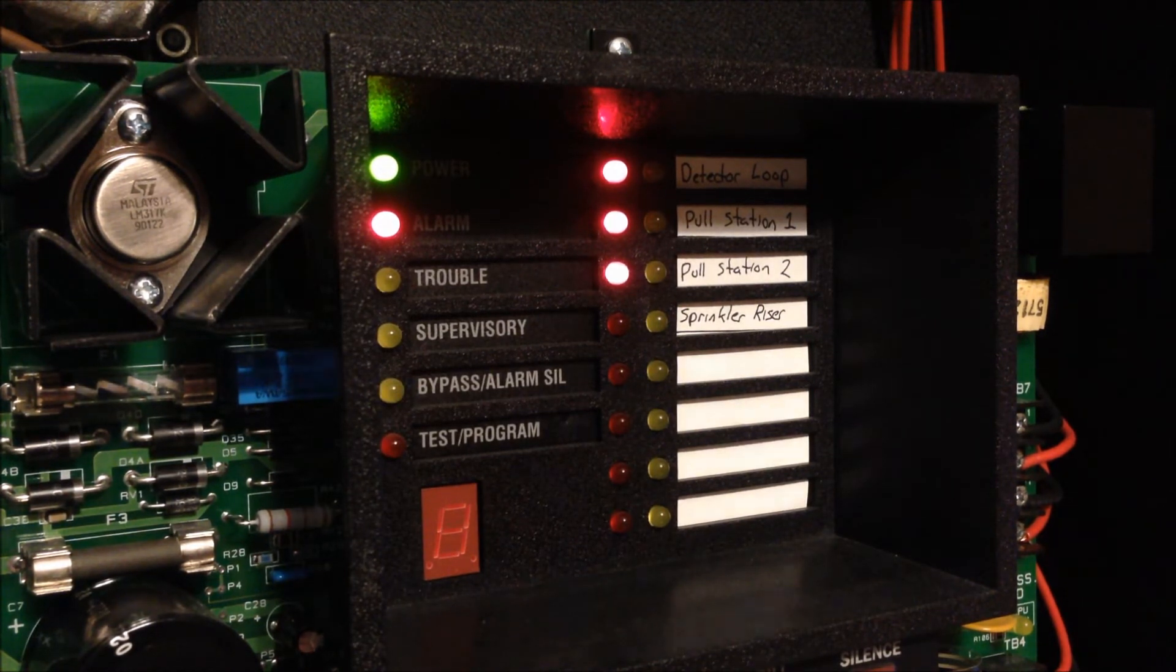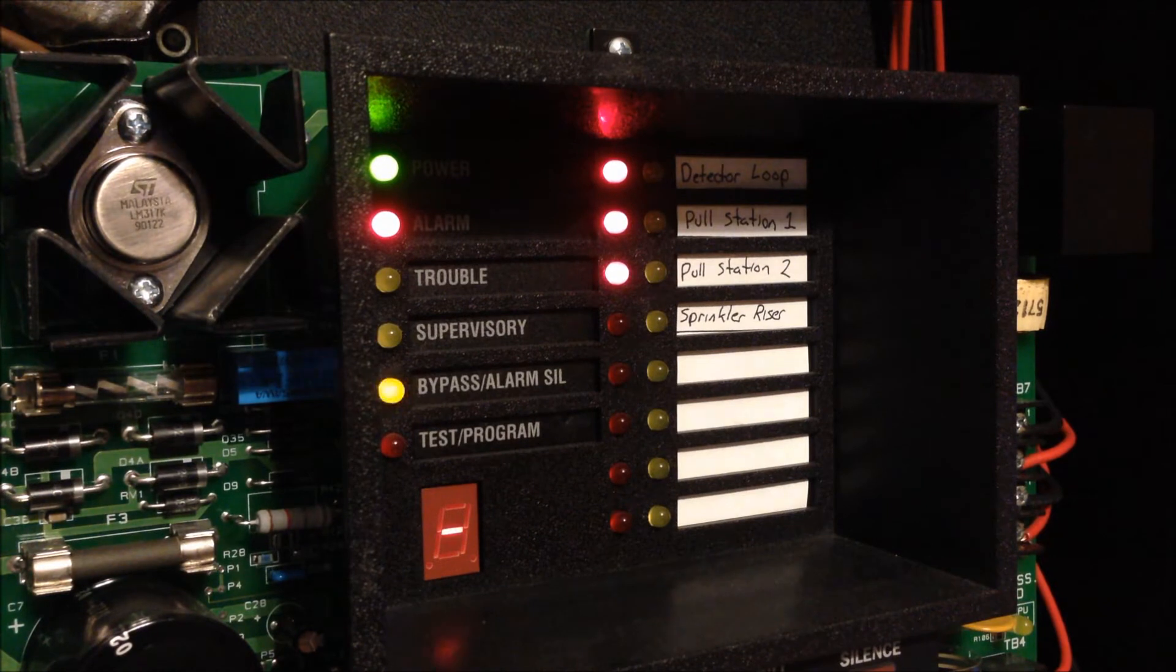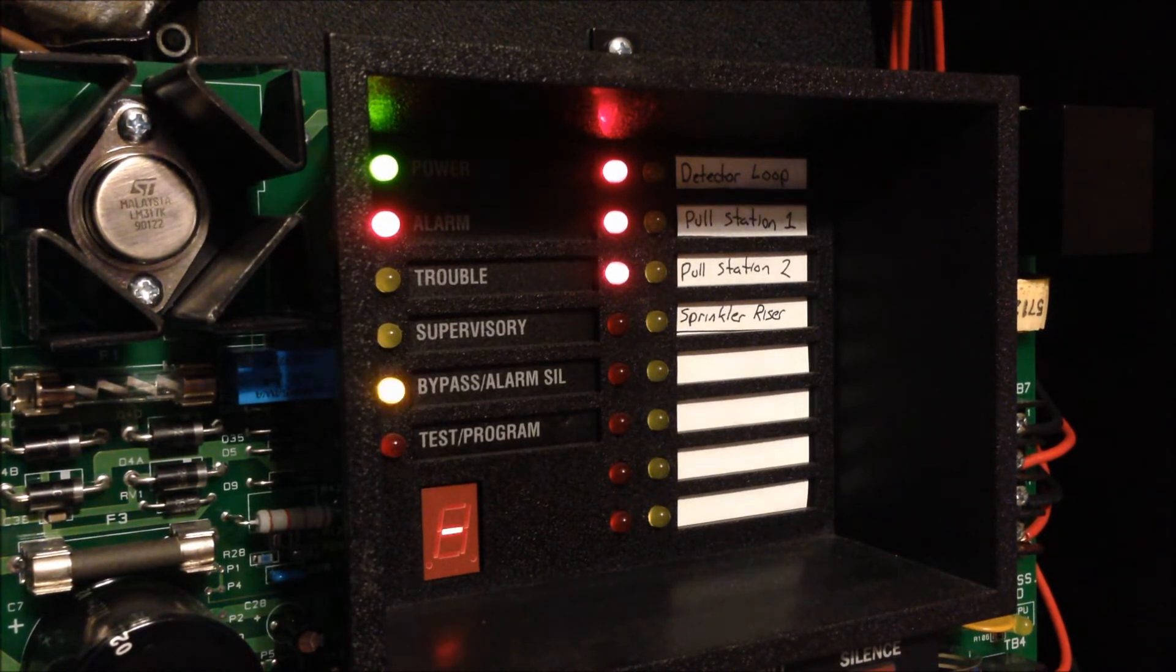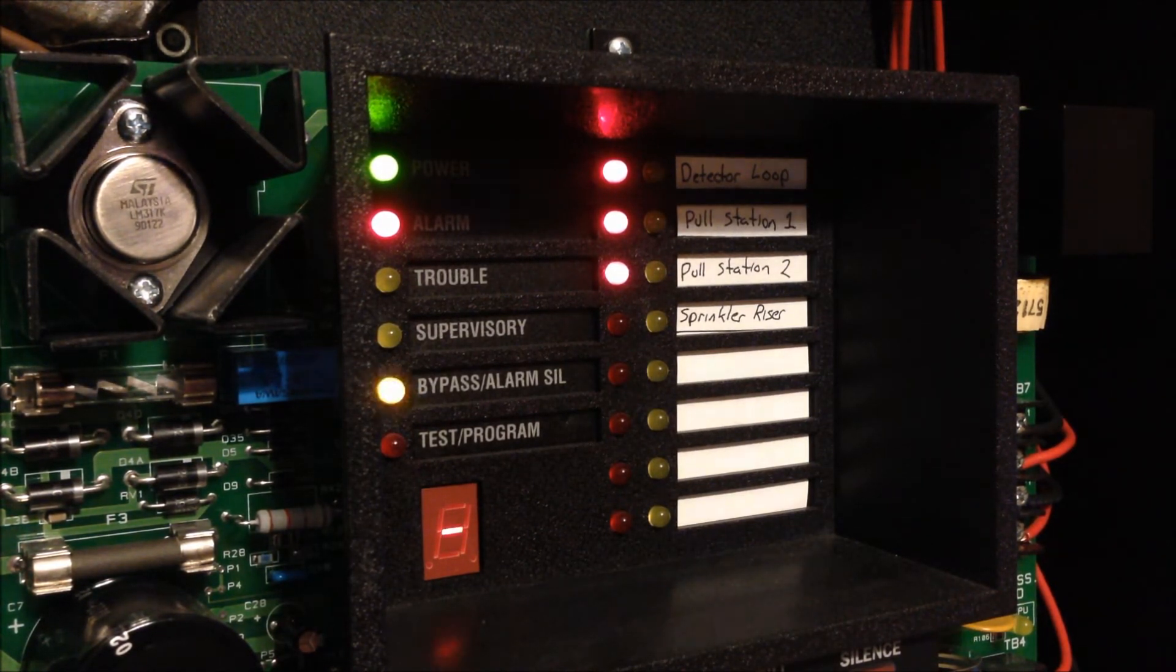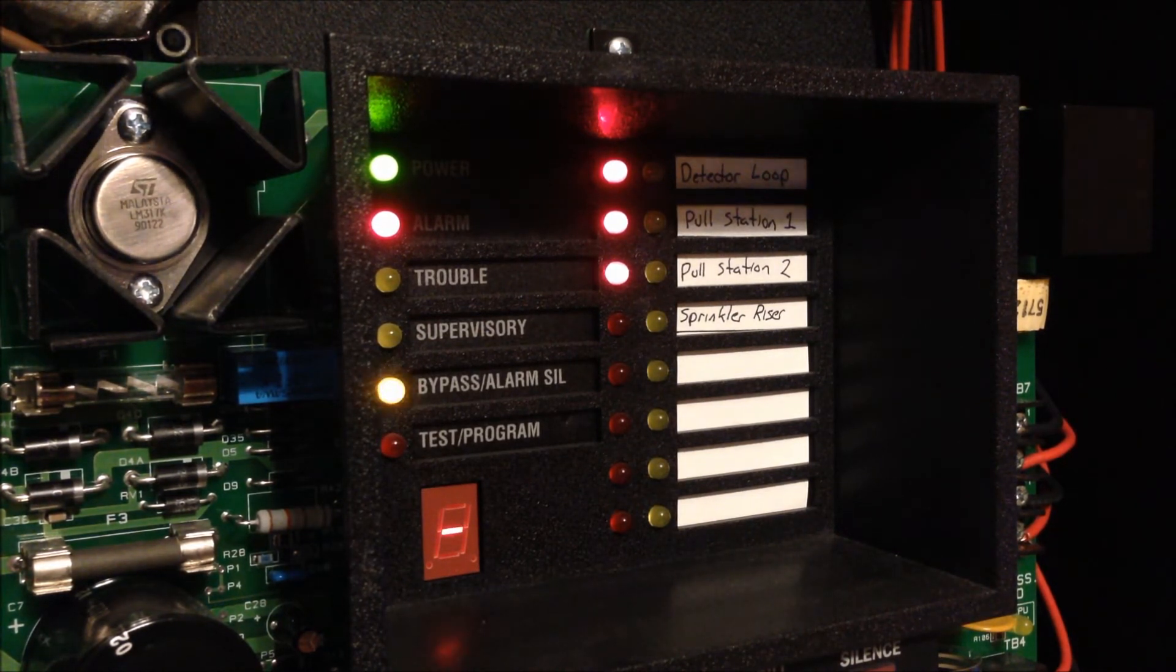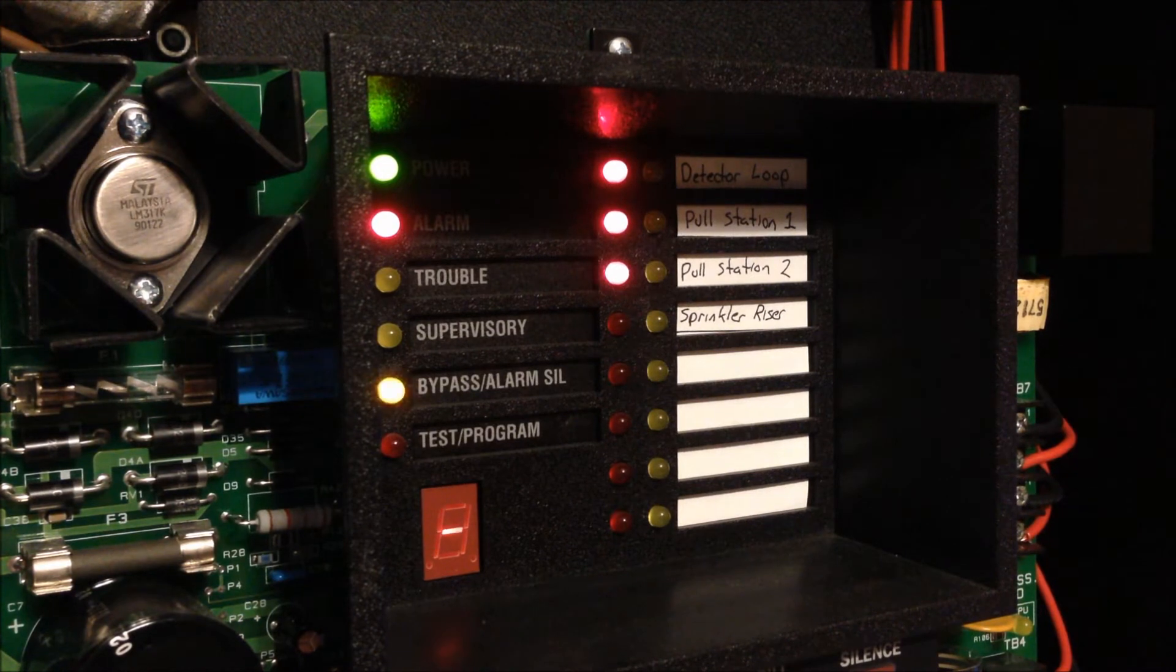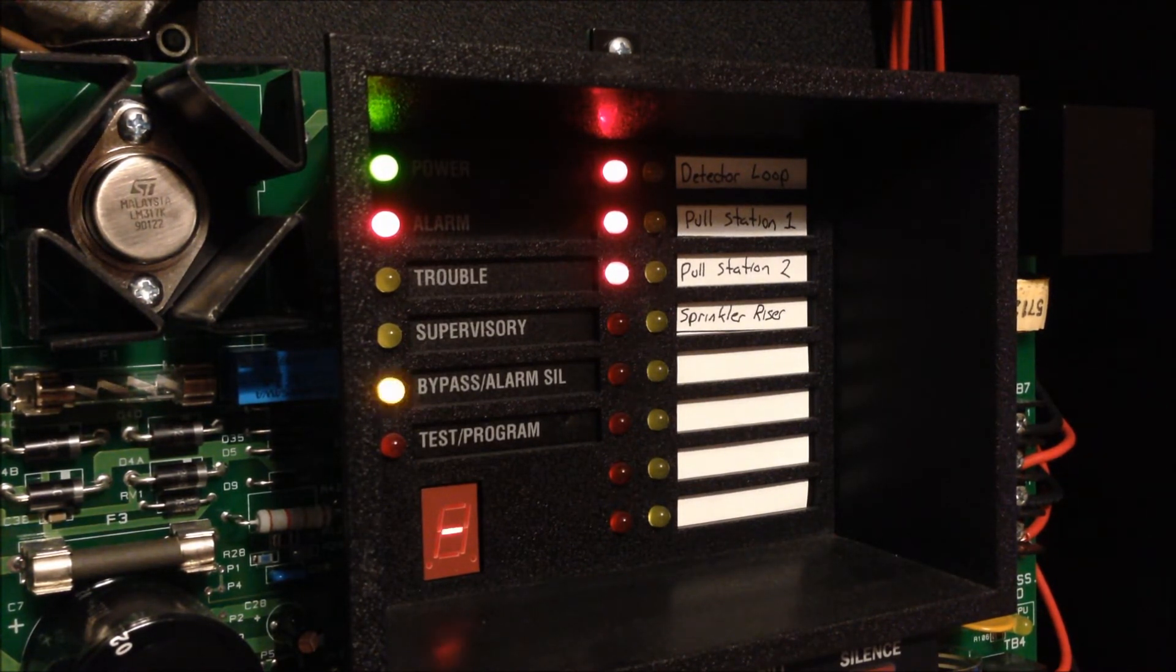So if zone 1, 2, and 3 are in alarm here even though I activated them out of order—activated zone 2 then zone 3 then zone 1—it will default back to doing zone 1, zone 2, then zone 3.